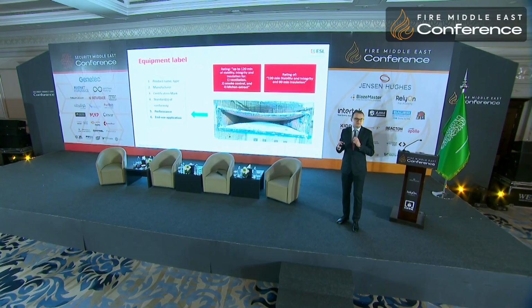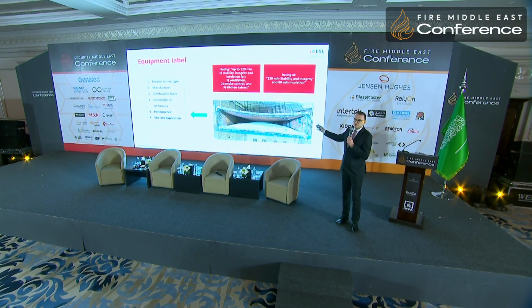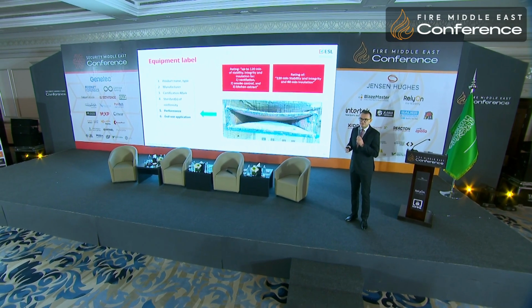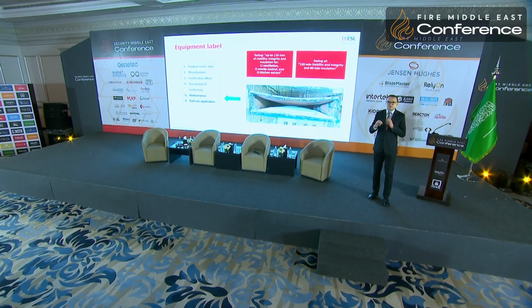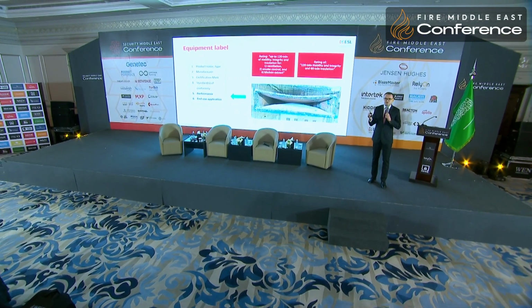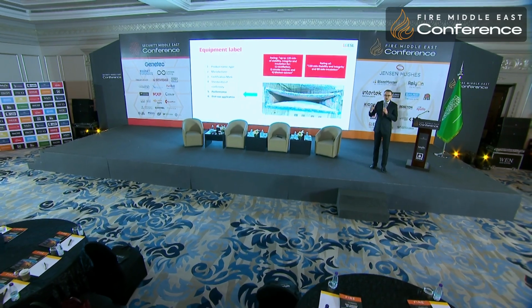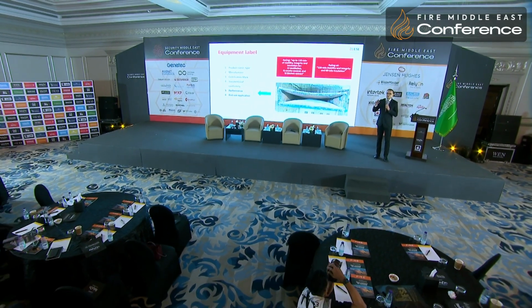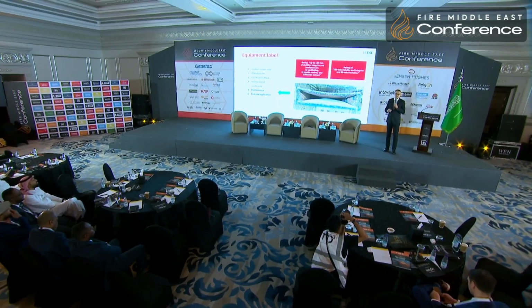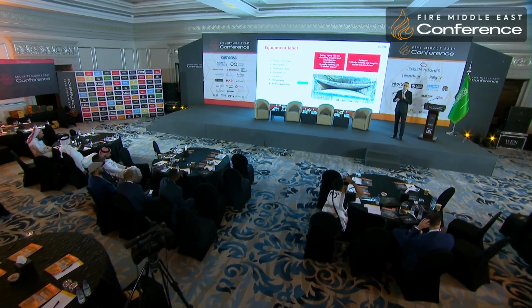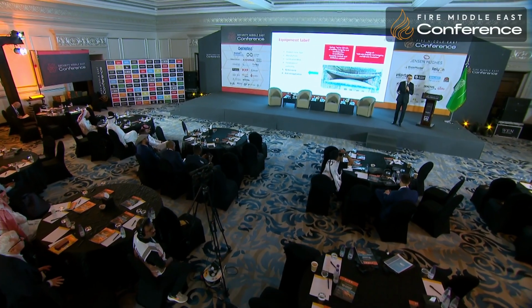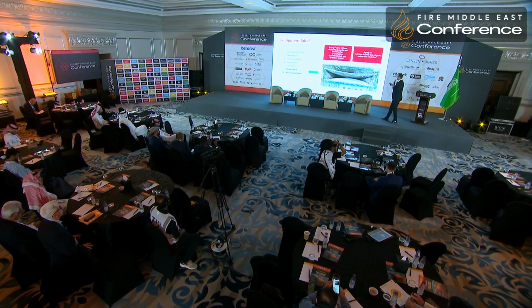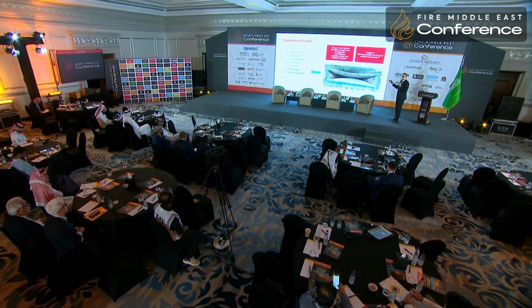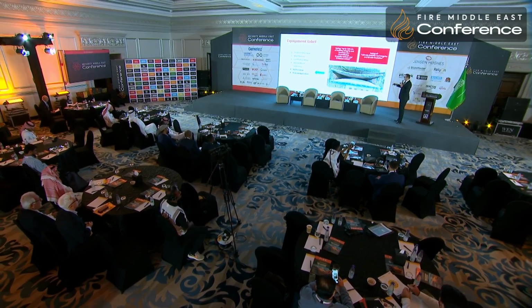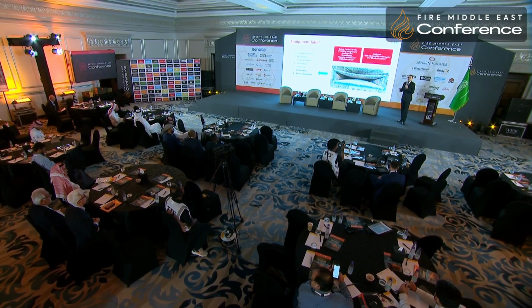And a practical explanation. This is a photograph representing the duct after completion of the fire resistance test in a furnace. You can see that the duct remained in place, didn't collapse, and didn't show any signs of cracks. However, its rectangular shape got modified. The cross section of the duct got significantly reduced, which means it will prevent the proper transportation of smoke if it's used for smoke exhaust. In that case, if the duct was tested for 120 minutes, this aspect of smoke control might have failed before.